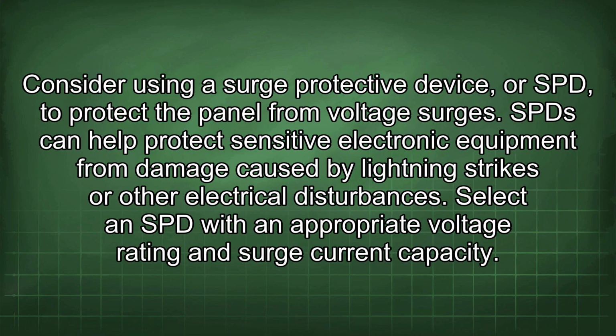Consider using a surge protective device, or SPD, to protect the panel from voltage surges. An SPD can help protect sensitive electronic equipment from damage caused by lightning strikes or other electrical disturbances. Select an SPD with an appropriate voltage rating and surge current capacity.